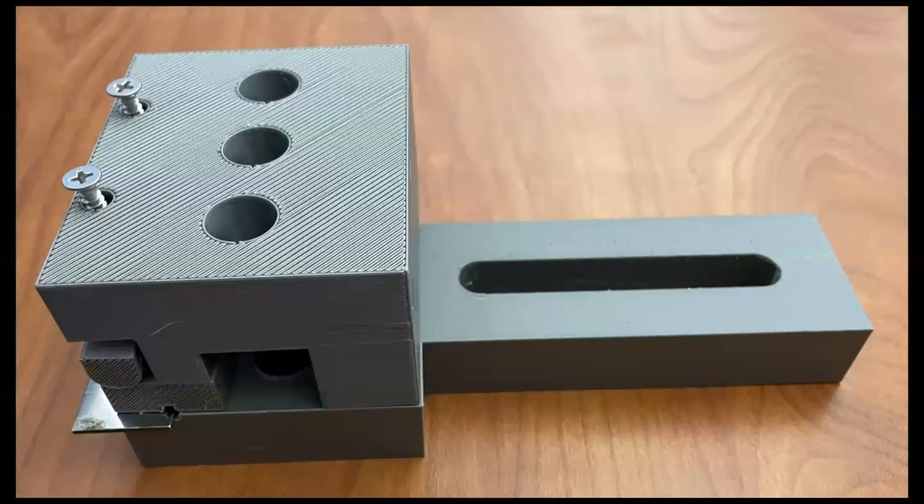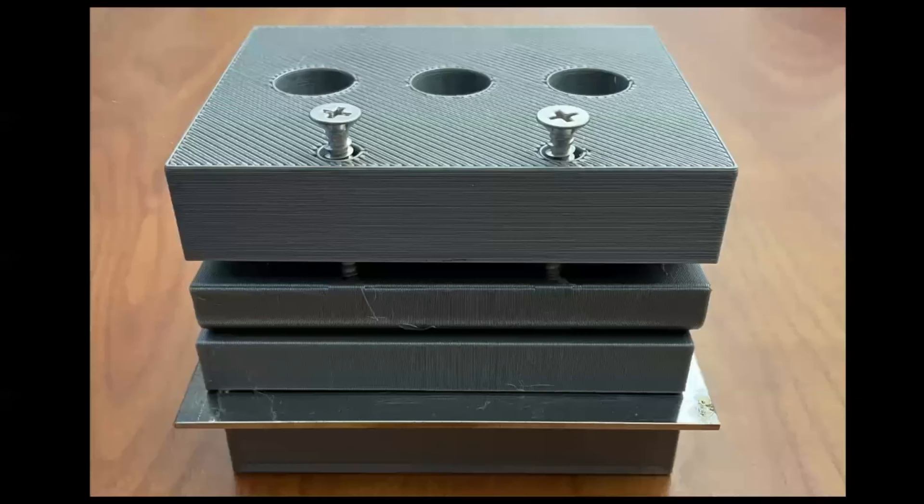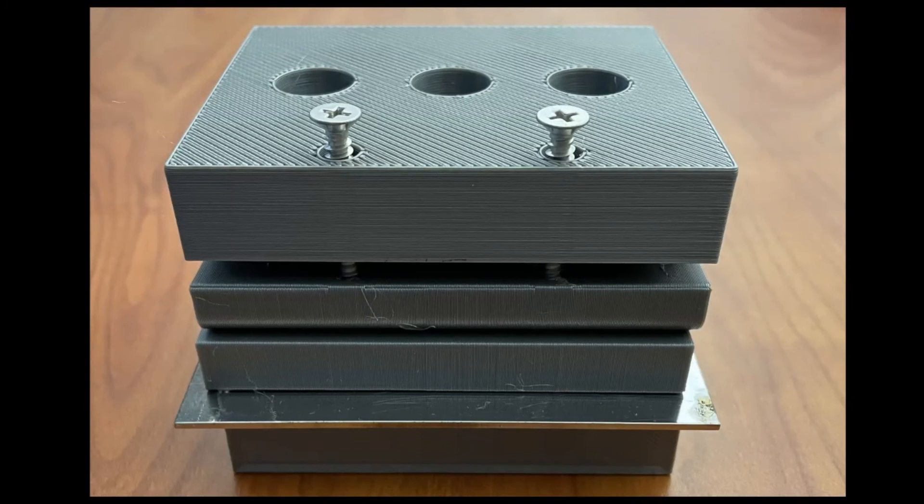Our clamps address this issue by applying pressure directly to the contact bases. We are utilizing a strong back and tensioning rod to pull the clamp together. We then use bolts at the front and a push bar to apply line contact across the entire front face of the clamp. This should apply enough force and a good contact surface to conduct the 3,000 amps, as well as removing any long-term deformation issue.